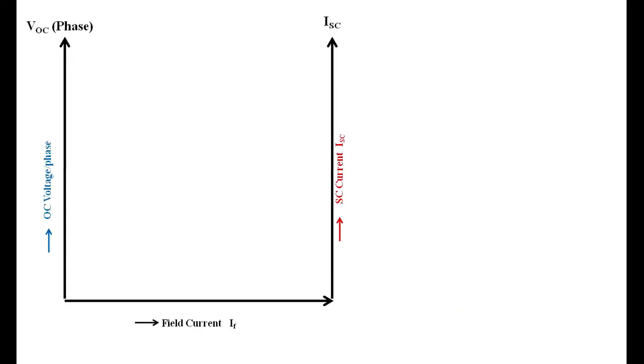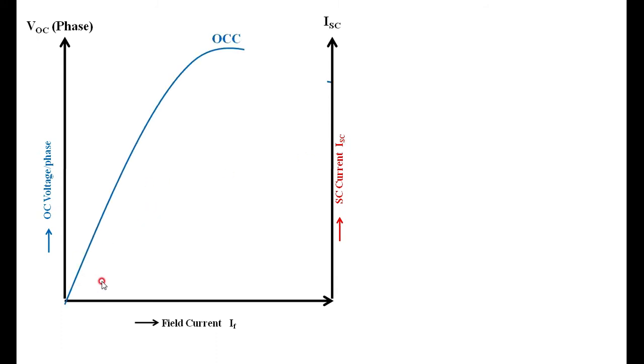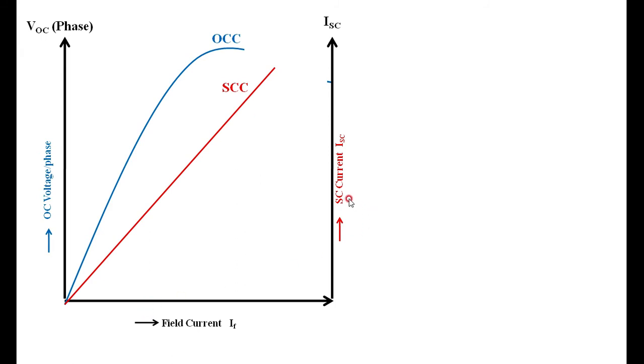To summarize the graphical procedure: first, take the field current as the common base. On one Y-axis, take the open circuit voltage (VOC); on the other, take the short circuit current with a different scale. Draw the open circuit characteristics by marking points for different values of field current against the corresponding open circuit voltage. Similarly, draw the short circuit characteristics using the same field current values.